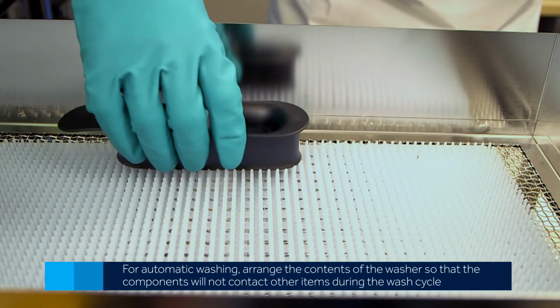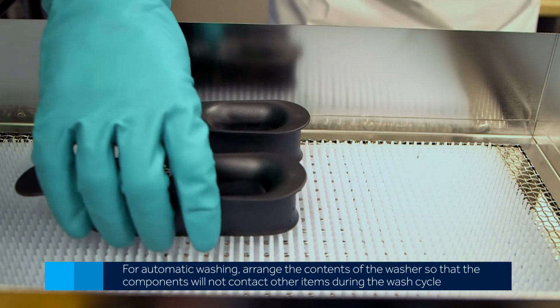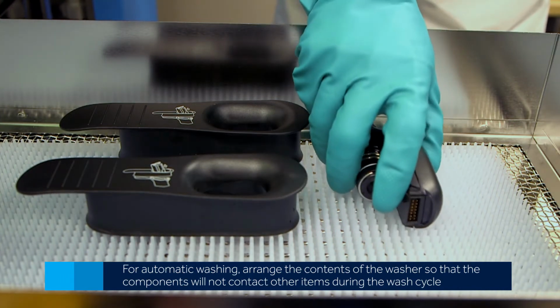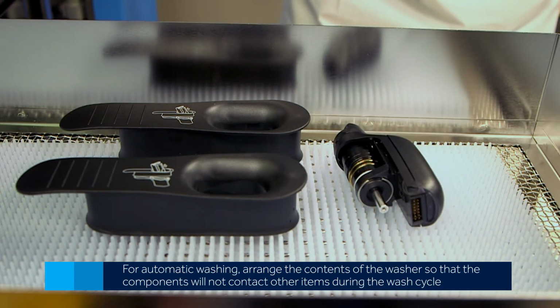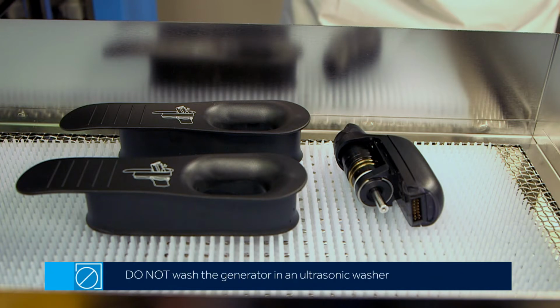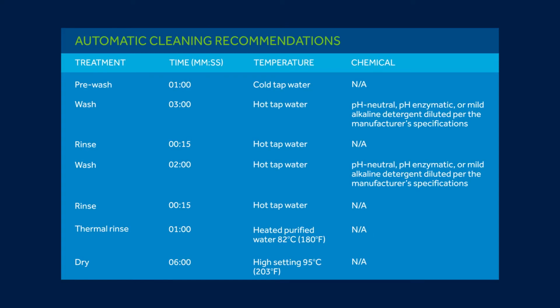For automatic washing, arrange the contents of the washer so that the generator and battery insertion guides will not contact other items during the wash cycle to avoid mechanical damage. Do not wash the generator in an ultrasonic washer. For automatic cleaning, run the automatic cleaning cycle. Note, the components have been qualified to withstand the following parameters: pre-wash of 4 minutes, total wash of 10 minutes, hot tap water rinse of 5 minutes, thermal rinse of 95 degrees Celsius, and dry time of 30 minutes.